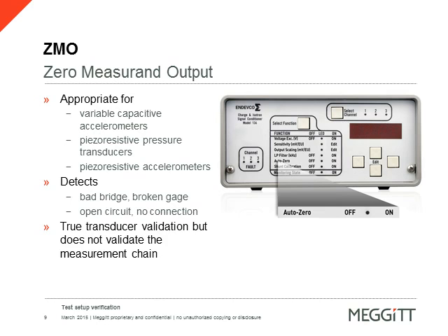Depending on the signal conditioner being used, the methods to do this test may be different in setup. For example, the Meggitt Model 136 signal conditioner can be set up with the auto zero turned off, and the ZMO can be measured at the output of the signal conditioner or by the data system. This directly tests the transducer itself along with the immediate measurement chain. Tim, would you like to expand on this?